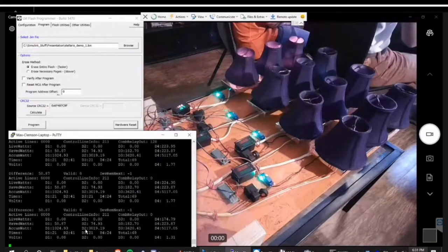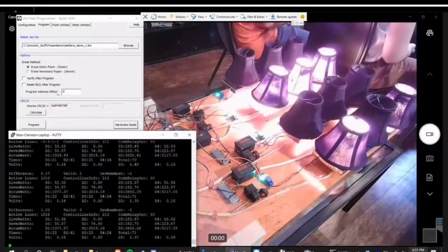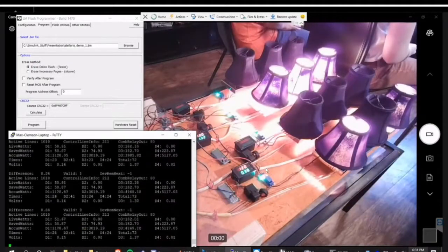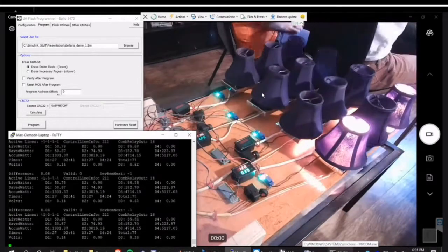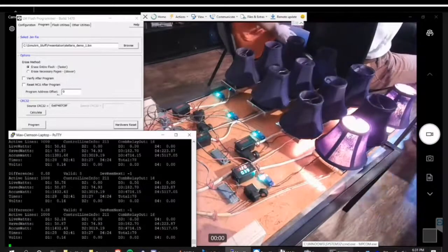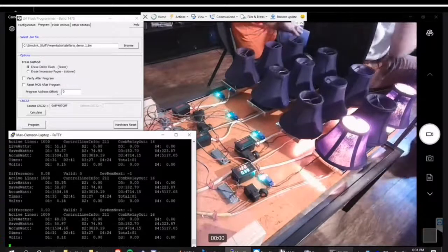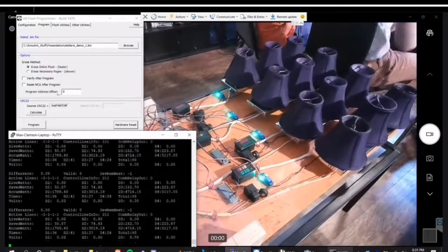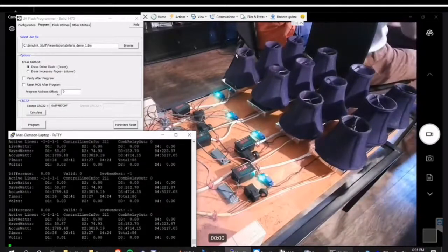And what we notice here is that device 2 has also passed its goal. And so the only ones left are 1 and 3, which can run at the same time. Device 3 will then pass its goal now, and device 1 runs on its own to completion. Now that all 4 devices have had their energy goal satisfied, it turns off.